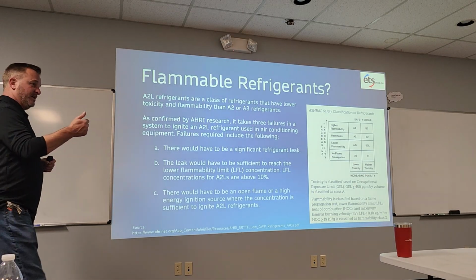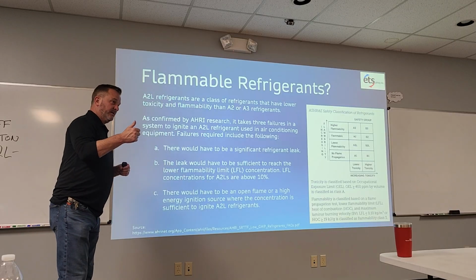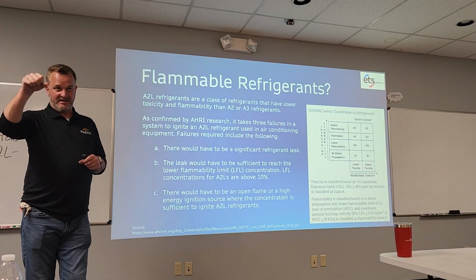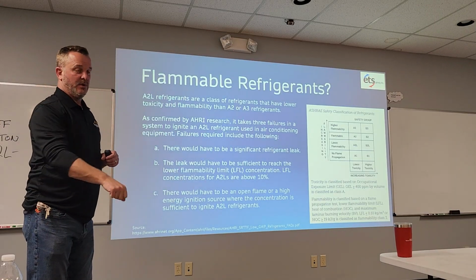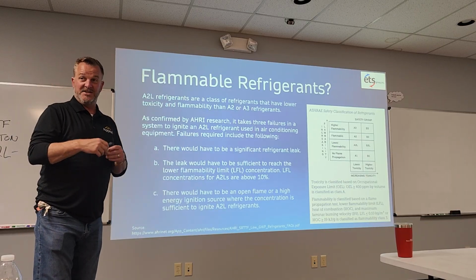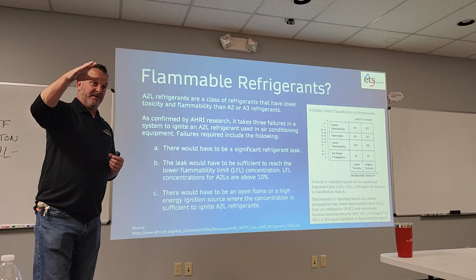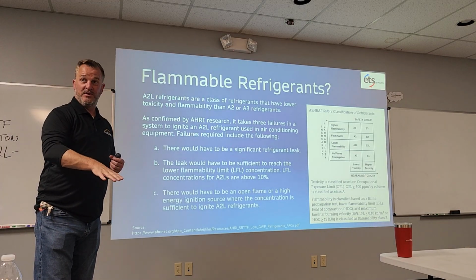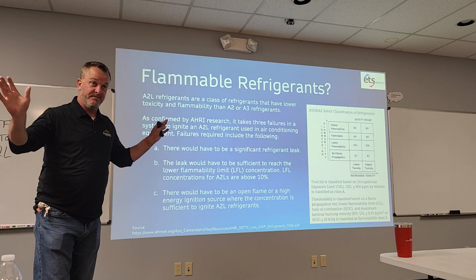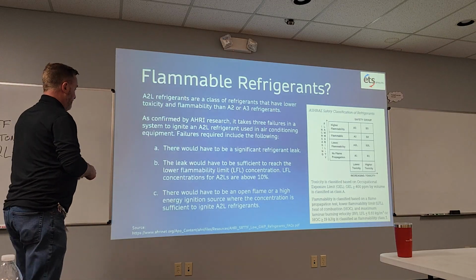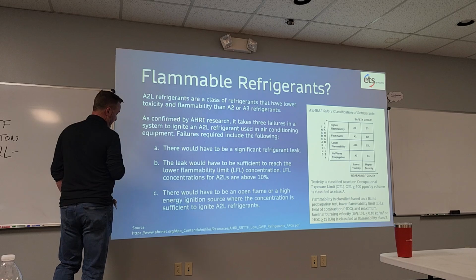You gotta remember, these A2Ls are heavier than air. So what's gonna happen is if there is a leak, it's gonna come out and slowly float down to the floor. Even if I was to light this stuff and actually get it lit, it's gonna be a slow blue flame that comes down. If it's puddled up on the floor, it's gonna do a slow blue flame and put itself out.